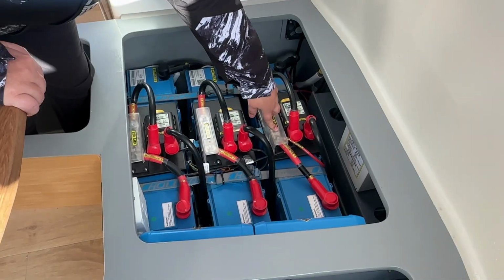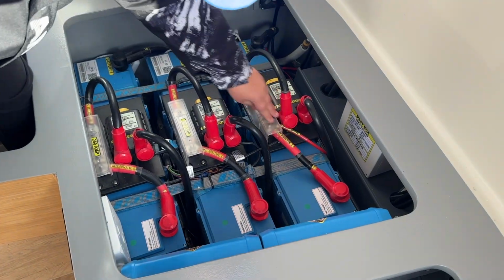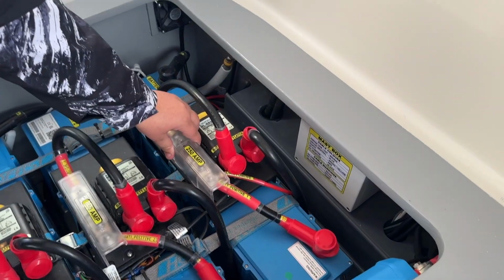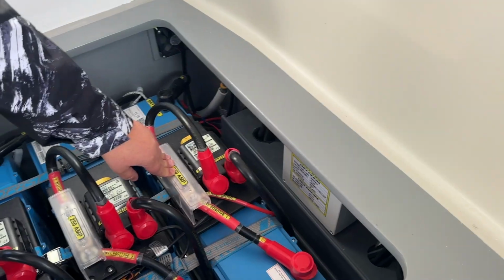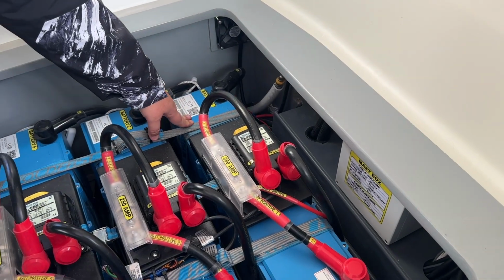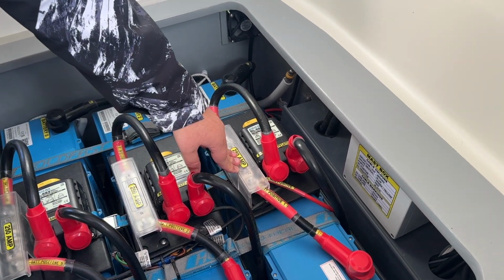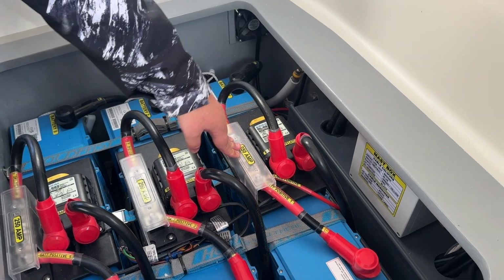Okay, cool. So you have your first line protection, which is a 250 amp class T fuse. Your battery is rated 200 amps, so this is why it's 250 amps, because the battery can spike.